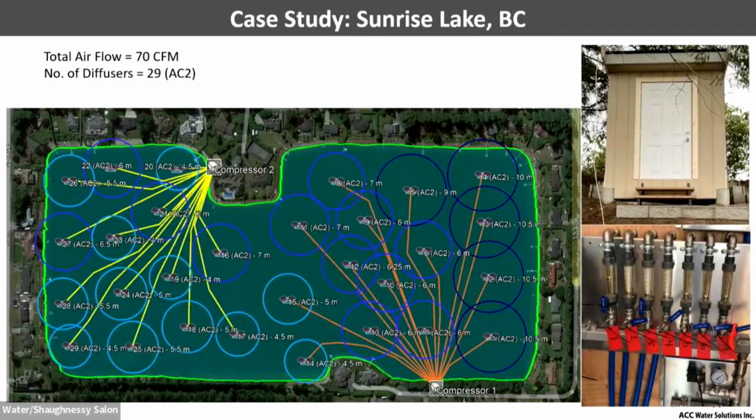There was no way, given the sheer size of the water body, that we were going to actually overcome the positive buoyancy of blue-green algae and mix it well enough to deal with the blue-green algae problem without it being a jacuzzi. It just would have been a rolling boil, which isn't realistic, both in terms of energy consumption and capital cost up front. It just wasn't realistic.